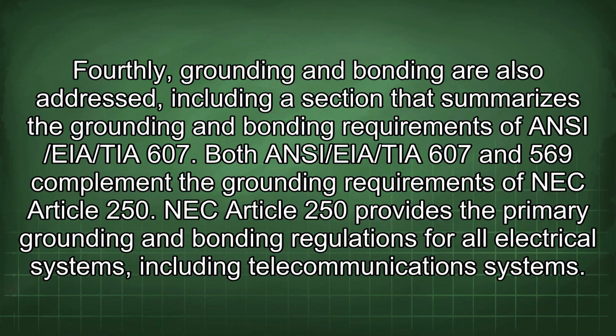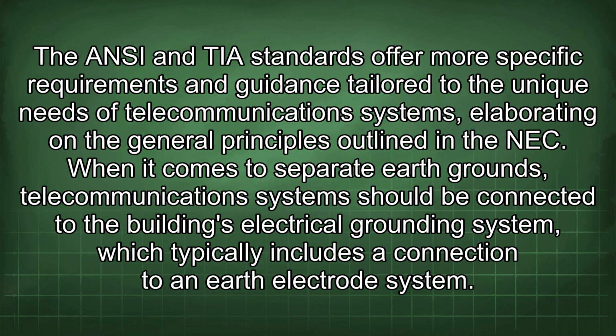Both ANSI/EIA/TIA 607 and 569 complement the grounding requirements of NEC Article 250. NEC Article 250 provides the primary grounding and bonding regulations for all electrical systems, including telecommunications systems. The ANSI and TIA standards offer more specific requirements and guidance tailored to the unique needs of telecommunications systems, elaborating on the general principles outlined in the NEC.